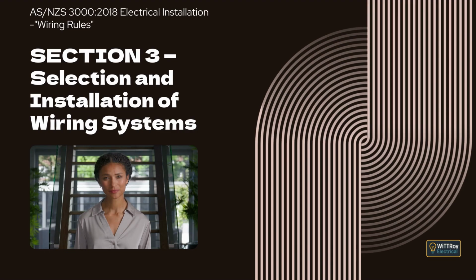Clause 3.3.2.3 Water or high humidity. This clause requires wiring systems to be selected and installed so that moisture or water entry does not cause damage. Where water may collect or condensation may form and create a hazard, provision must be made for safe drainage. Where wiring systems may be exposed to wave action or moving water, protection against excessive flexing and mechanical damage must be provided in line with the relevant clauses.